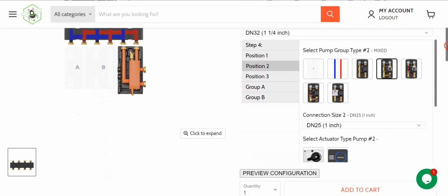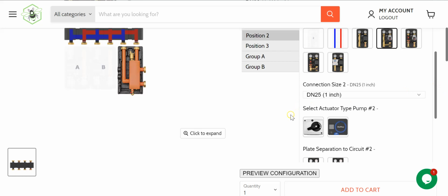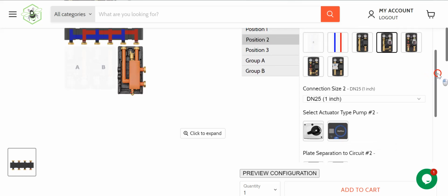And this is then going to give me more options. Lots of different actuators available. This is just showing 2. Standard actuator, 230 volt, motor open, motor close. This is used when connecting to Viessmann, Baxi boilers, for example. Or this is the NWR3 Flamco version. This is a standalone weather compensated actuator, which has an inbuilt screen for making all your selections here, setting the curve, and different time parameters, temperatures and everything from the screen itself.